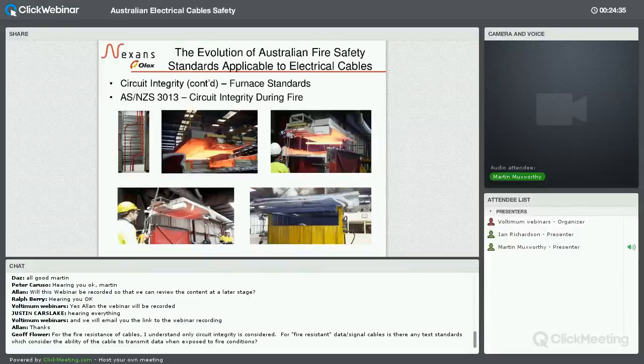This furnace is an enclosed furnace, several meters long and probably a meter deep, for example. So it's quite a significant size furnace, and what you're seeing here is the lid of the furnace being lowered into an area where it will be sprayed by a water spray, and it's got to survive a water spray for about 60 minutes, I think it is.